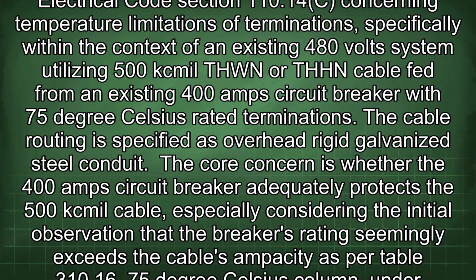Let's delve into the interpretation of National Electrical Code Section 110.14(C) concerning temperature limitations of terminations, specifically within the context of an existing 480-volt system utilizing 500 kcmil THWN or THHN cable fed from an existing 400 amp circuit breaker with 75 degrees Celsius rated terminations. The cable routing is specified as overhead rigid galvanized steel conduit.